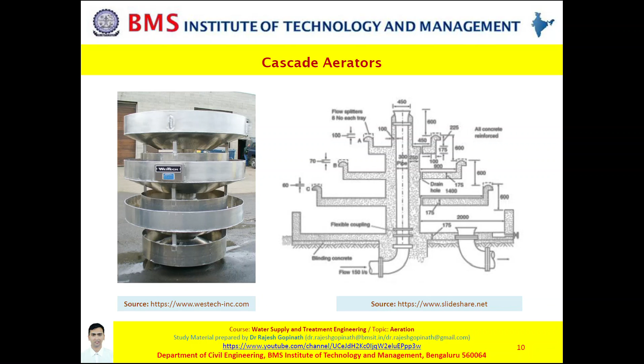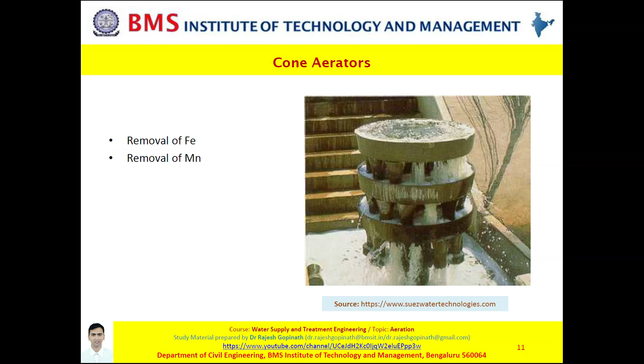As you can see in the image, its appearance is much different from cascade aerators, wherein the water was falling from one step to another. But here the water is pumped to the top of the cones and then it is allowed to cascade down through the aerator. This kind of aerator is primarily used to oxidize iron and manganese from the ferrous state to the ferric state. This is necessary before you go in for filtration. As you know, iron and manganese coexist and they tend to impart stains and color, reddish in the case of iron and grayish in the case of manganese.